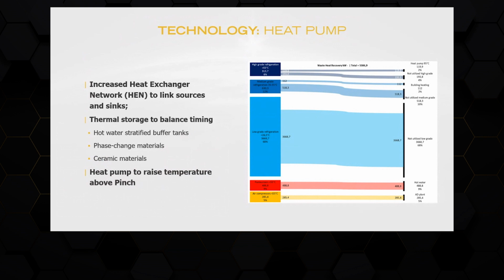Based on the heat mapping to optimize energy use, we did pinch analysis and we designed a new heat exchanger network that included additional storage tanks, heat exchangers, and temperature and flow control valves to ensure a uniform flow rate and temperature to users. We also identified locations where the temperature of heat sources was lower than that of heat sinks. For example, chilled water return coming from the plant was at 53 degrees Fahrenheit, whereas the lowest hot water temperature requirement for heating in a tank was 110 degrees Fahrenheit.